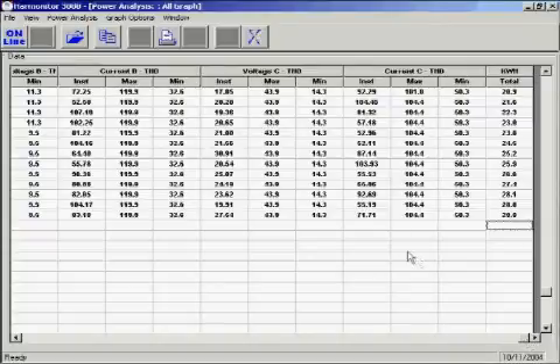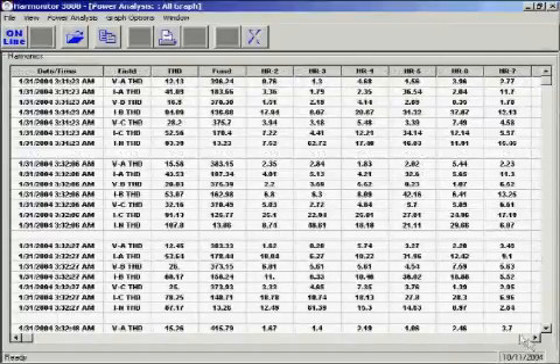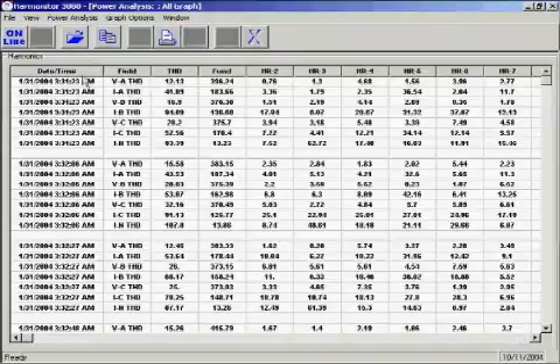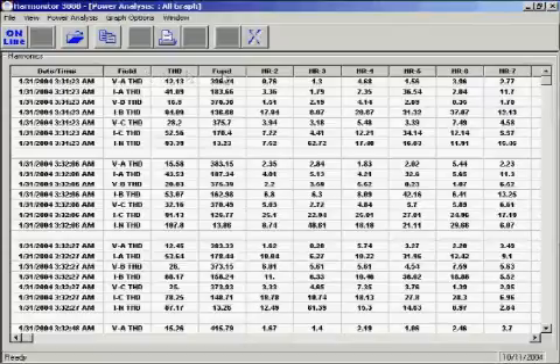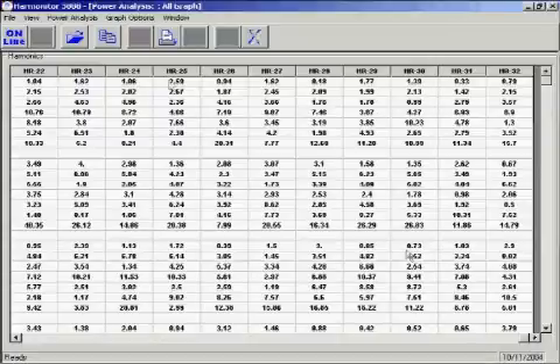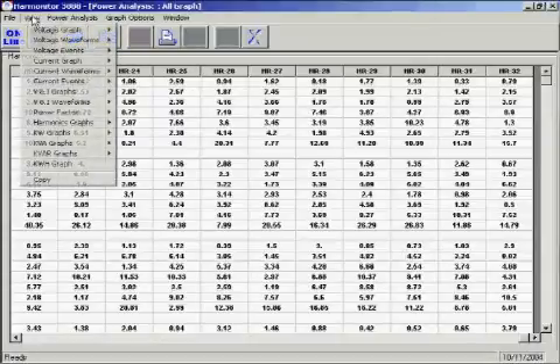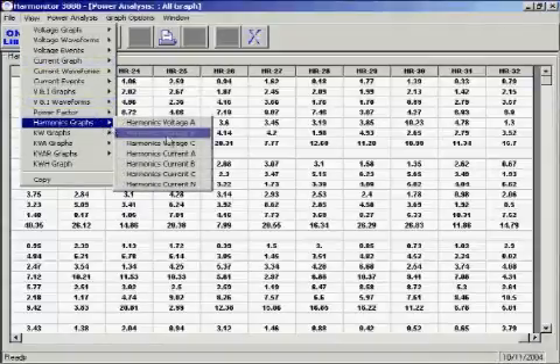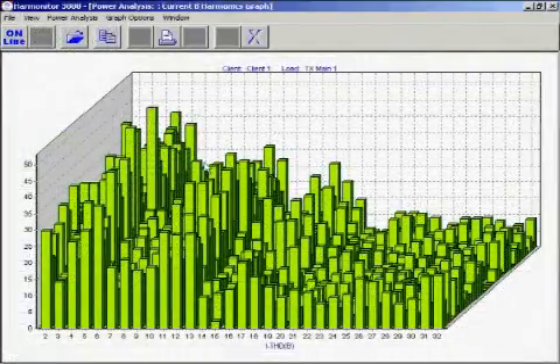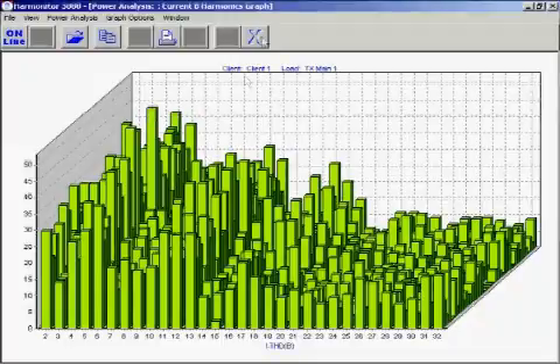To view individual harmonic information, double-click anywhere on the chart. Here, for both voltage and current, for each phase and each sample, we have total harmonic distortion, the magnitude of the fundamental, as well as a magnitude for each individual harmonic from the second to the 32nd harmonic. To see this information graphically, go to View, Harmonics Graphs, and choose the set of harmonics you wish to view. Seen here, we have the current harmonics for phase B. To close the window, click the X button.